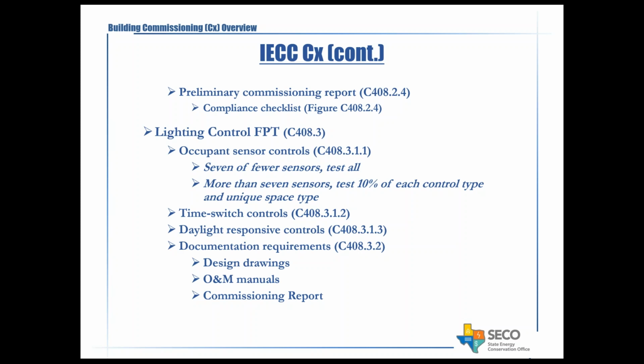At the same time, the code requires that if you have 7 or fewer occupancy sensors, you need to test them all. If there are more than 7 sensors, then test 10% of each control type and unique space type. So it's important to know that the code doesn't require you to test every one of them. Some people prefer that be done, and that could be part of the scope, but the code requires that you test 10% of unique types.